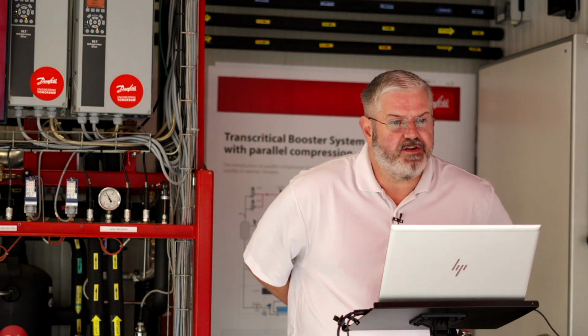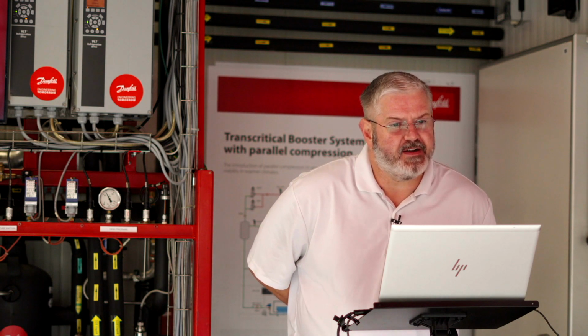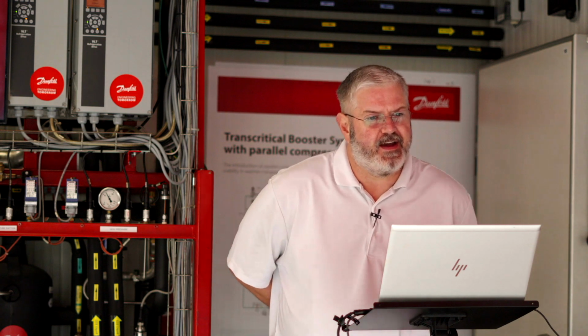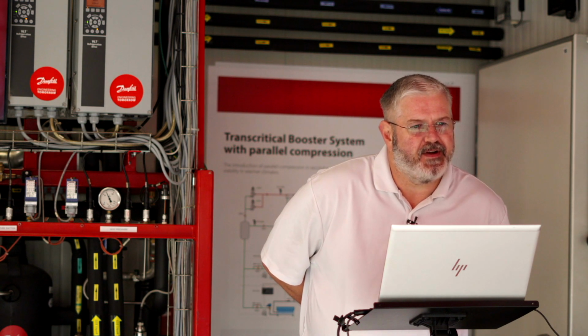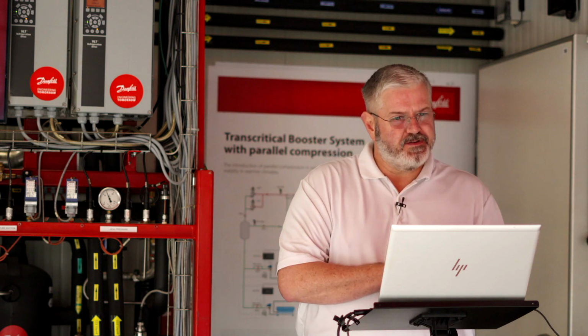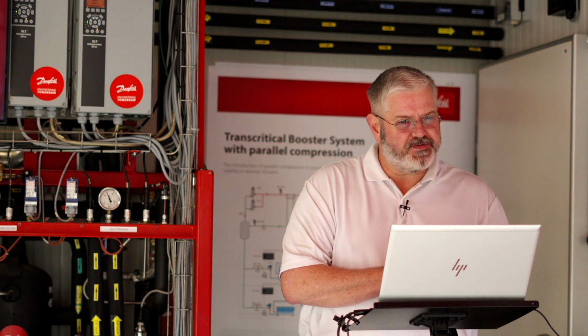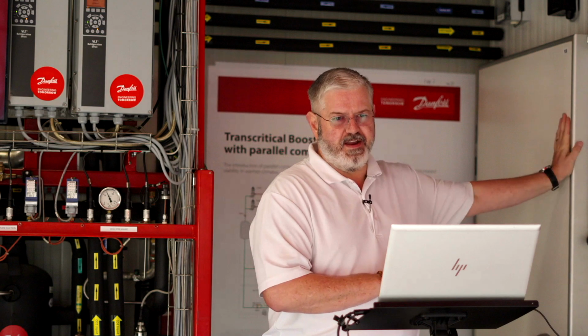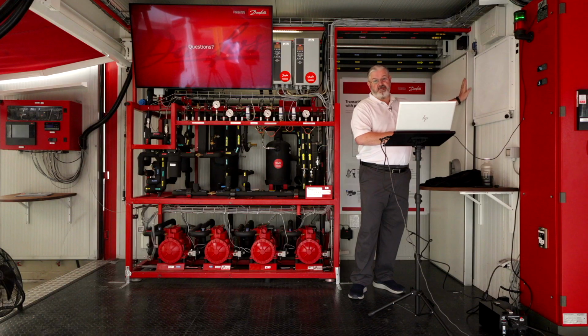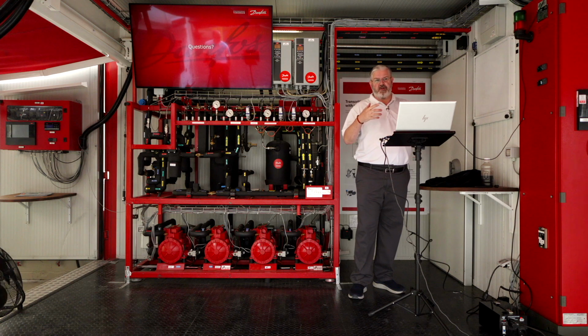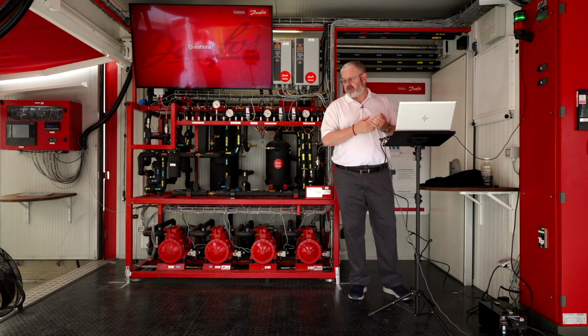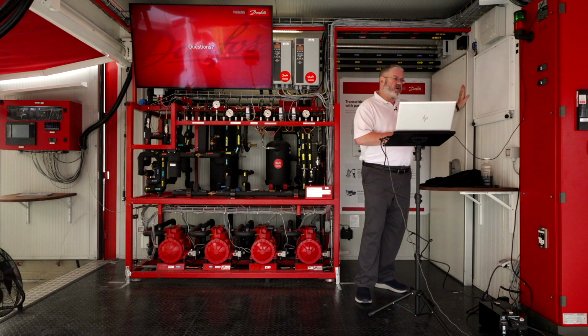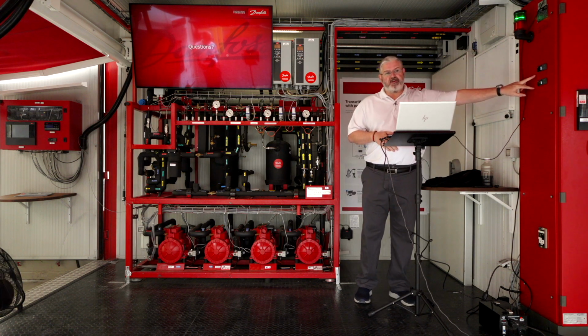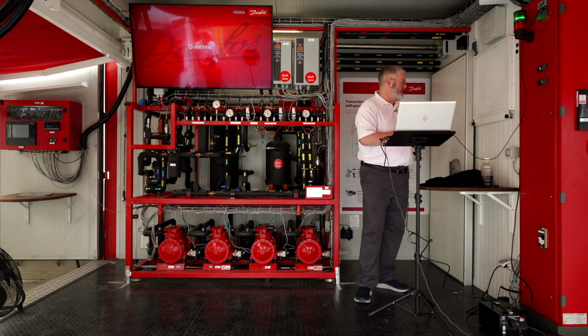So we have a question. Are you using the low temp evaporator as a low temp box, or is it used for refrigerant temperature control? Let me reread that. Okay. So they're asking if you're using the low temp evaporator as a box, or is it used for refrigerant temperature control? If the question is about the big red walk-in box on our training unit, this is actually medium temp. We didn't really have room in a 20-foot container to put either a low temp load or low temp compressors. But this is just a walk-in box. We've currently got it running at 35 degrees, pulled down to temp, so the system would run for today's training.